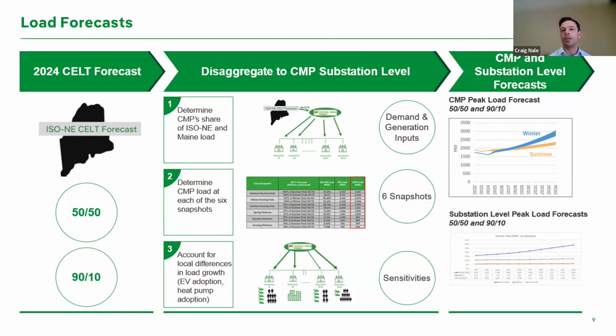People are switching from oil, gas, and propane to heat pumps. So we're seeing a very steady load throughout the winter, and it's an increasing load too. More and more, instead of planning for that summer peak with air conditioners running, we're planning for a very consistent and fairly long winter peak, and that's changing how we approach planning the system.